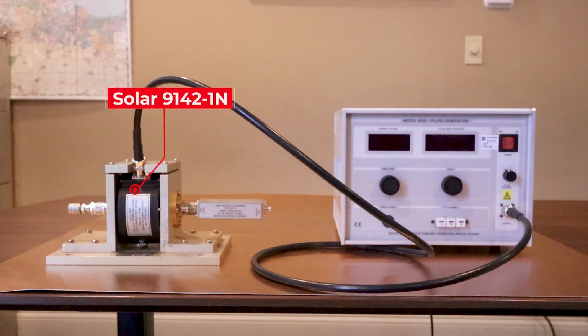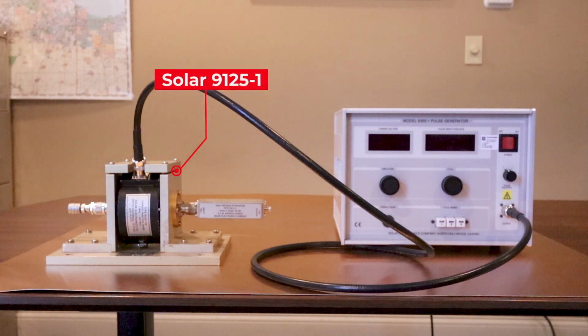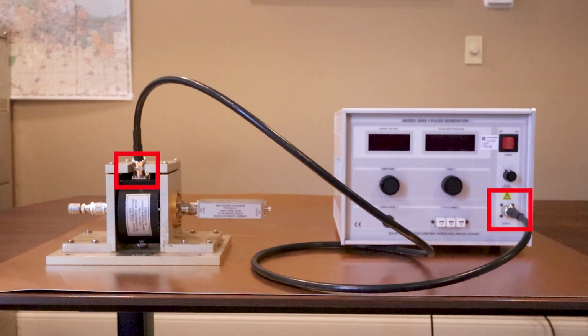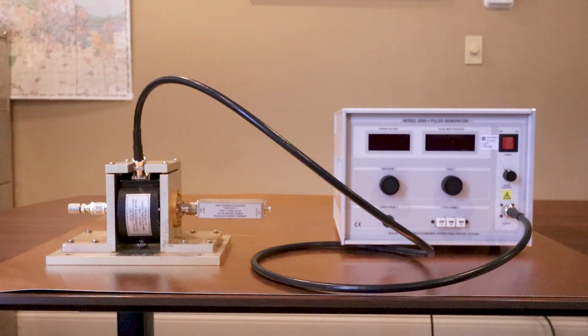The first items you will notice are the Solar 9142-1N. It's an injection probe. You can see it's kind of black there. And then we have it clamped around our silver or gold colored Solar 9125-1 calibration fixture. The input on the injection probe is connected to the output on our Solar 9355-1 transient generator, and that's going to be that type N output, and that's going to go through the calibration fixture. It has a little cutout on top and goes directly to our 9142-1N injection probe.